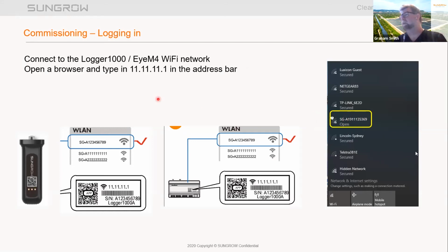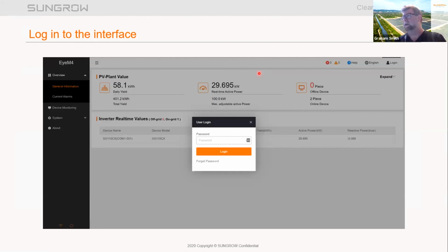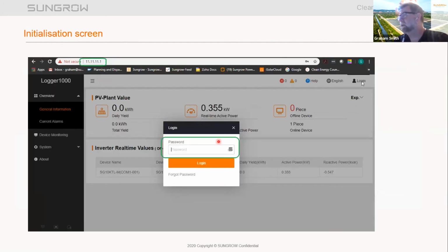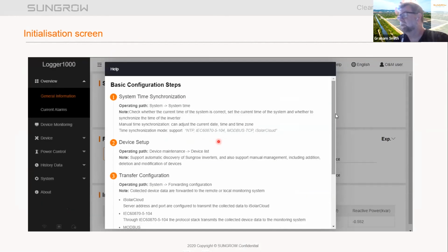You then open up a browser and you type in the address 11.11.11.1 into your address bar, and you will be into the interface. So this one here is an EyeM4, you can see it here. So you need to log in. So you just tap that little login and you enter down here, open up this one here, and the password is PW lowercase 1111.